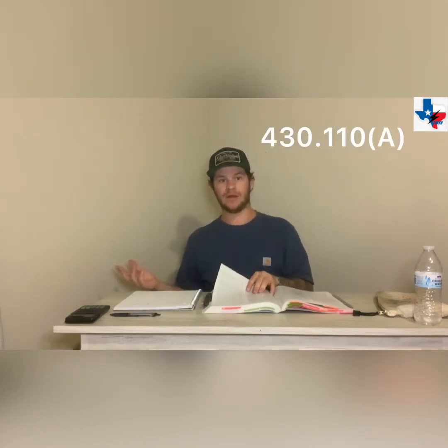And then the next one that we're going to be talking about is 430.110(A). 430.101, part 4 of 430, is your disconnecting means. So that's going to be your location of the disconnecting means, the controller, stuff like that. It goes into all of that. But 430.110 is the ampere and interrupting rating of the disconnect that you're going to be dealing with. And this tells us that we need to multiply by 115% of our FLC. Well, the problem with this lies in that you could have, say, a 100 amp FLC.